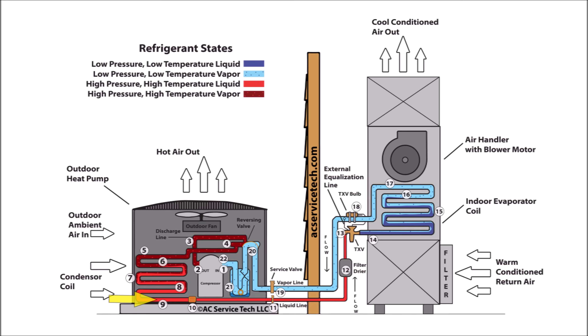In step ten, the high pressure, high temperature, subcooled liquid bypasses through and around the inactive metering device and remains unchanged. The liquid refrigerant continues to reject heat and lower in temperature until it exits the outdoor unit at step eleven. Step eleven is where you can read the high pressure, high temperature liquid refrigerant pressure — there is typically an access port on the side of the liquid line service valve. The temperature decrease of the liquid refrigerant between step eight and step eleven is called the subcooling.